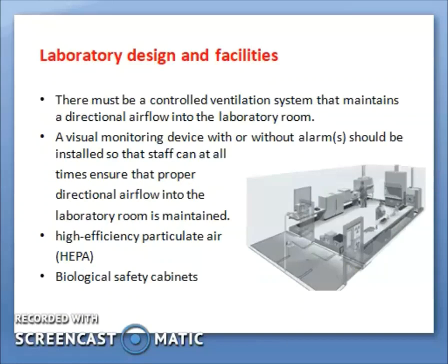In the design of a biosafety level 3 lab, there must be a controlled ventilation system that maintains a directional airflow into the lab room. A visual monitoring device with or without alarm should be installed so that staff can at all times ensure that proper directional airflow into the lab room is maintained.